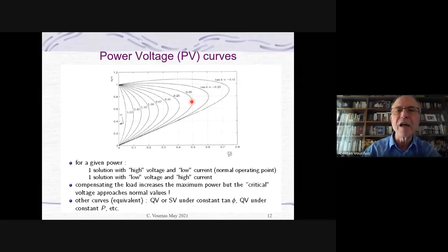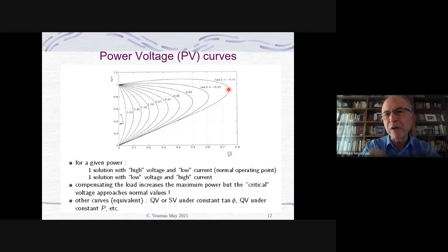If I go to a negative tangent, meaning the load is consuming P but producing Q, reactive power, I have an over voltage, and I increase both the maximum power transfer and the voltage at which I have my maximum power. As we'll see, this maximum power will also be the limit of voltage stability.